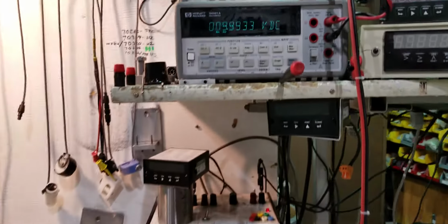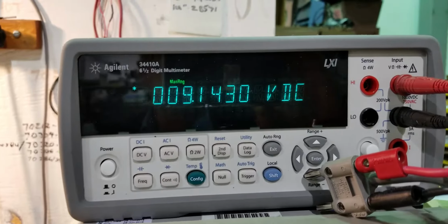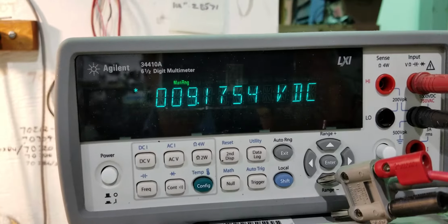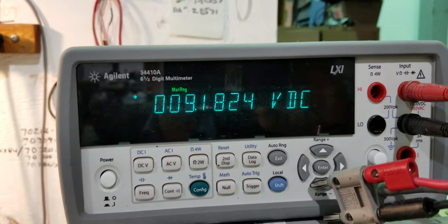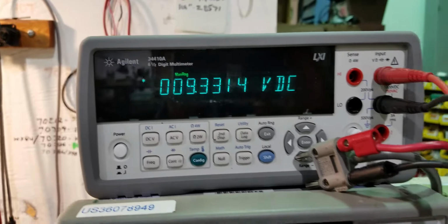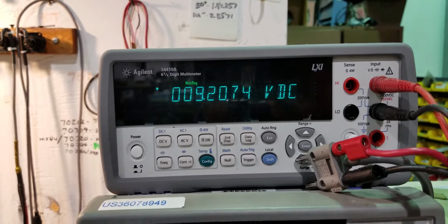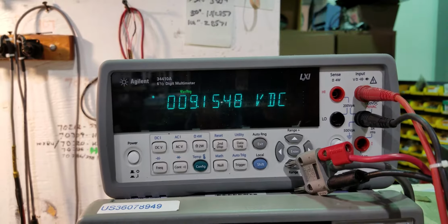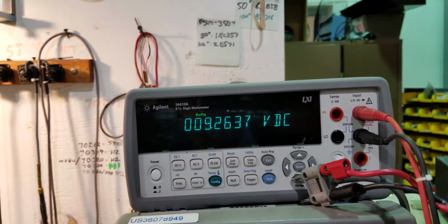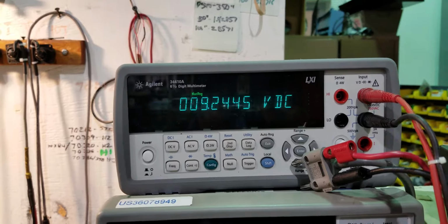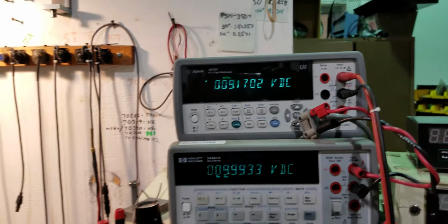The voltage that I'm getting out of it is substantially lower. On this Agilent meter here, it's reading about 9.25 volts or thereabouts. It's moving around a lot, but it's nowhere near 10 volts, which is where it should be. And in this one range, which is the 0 to 1,000 count range, it seems like the output voltage at the top is significantly less than it should be. It should be 10 volts ideally, or thereabouts, close to 10 volts.